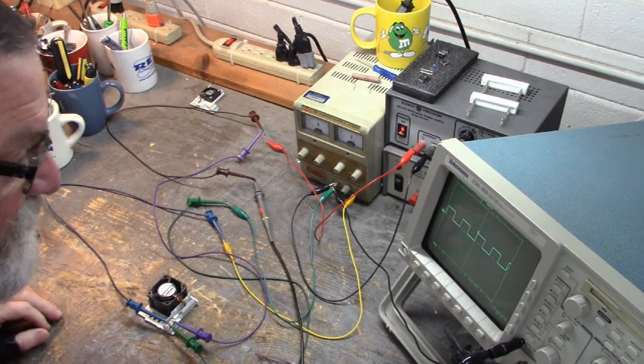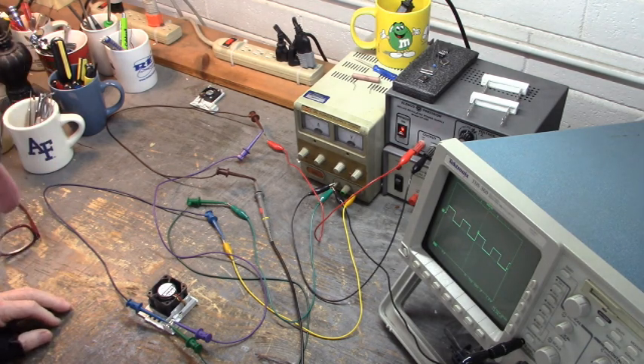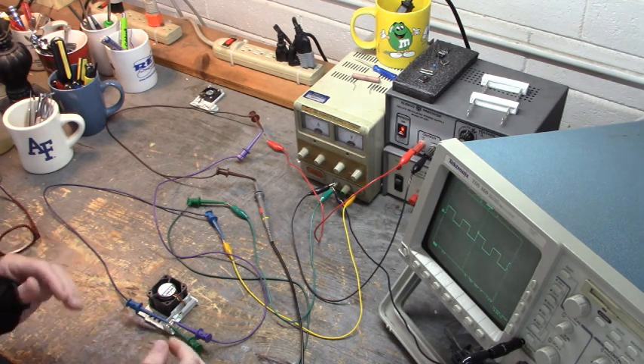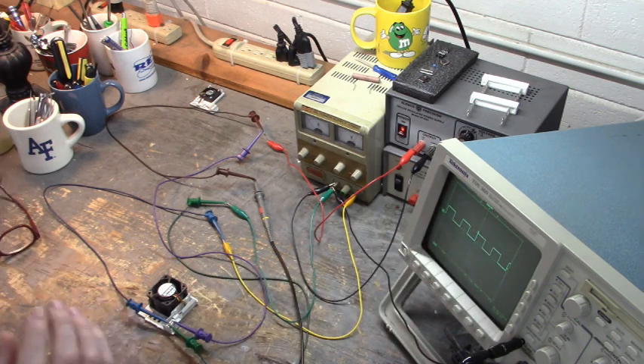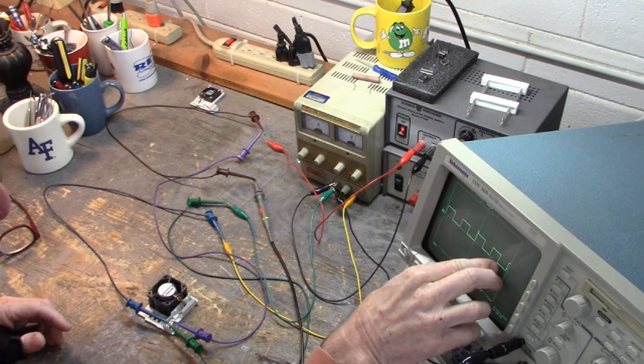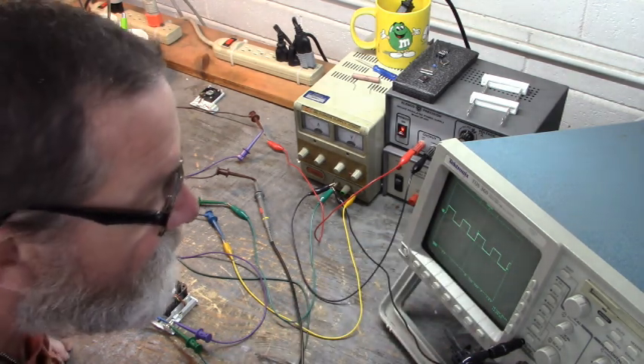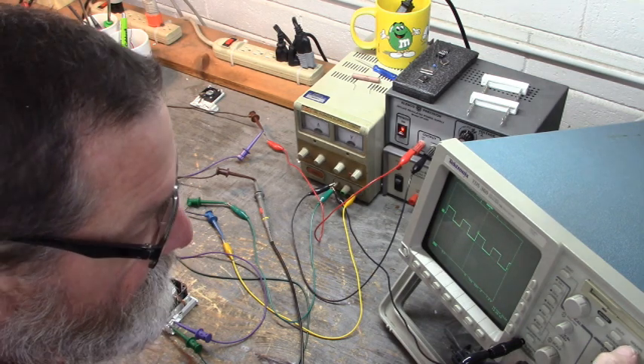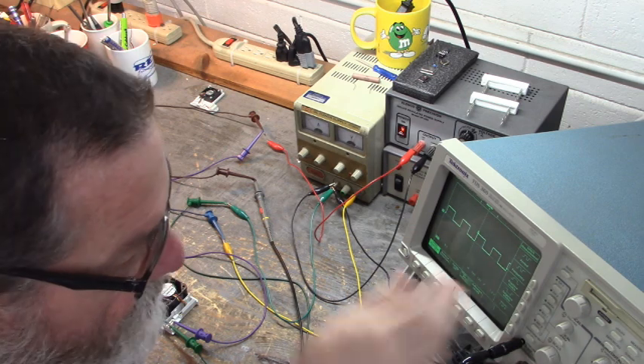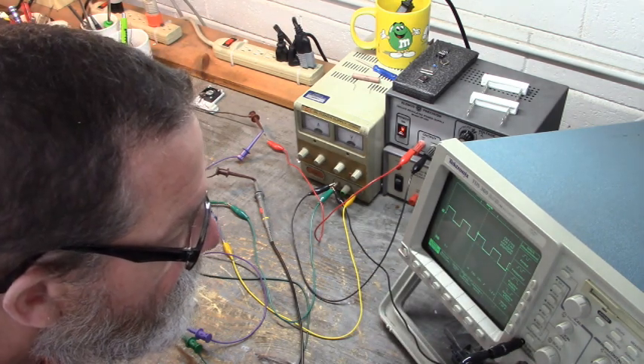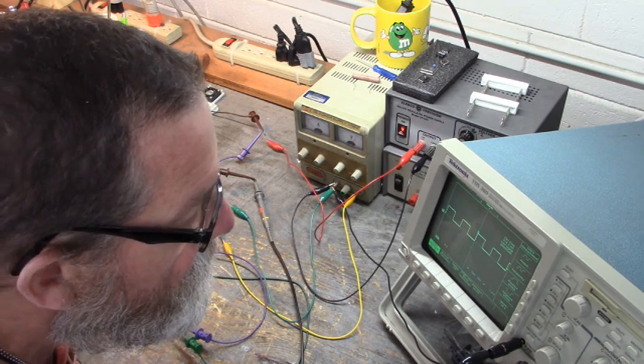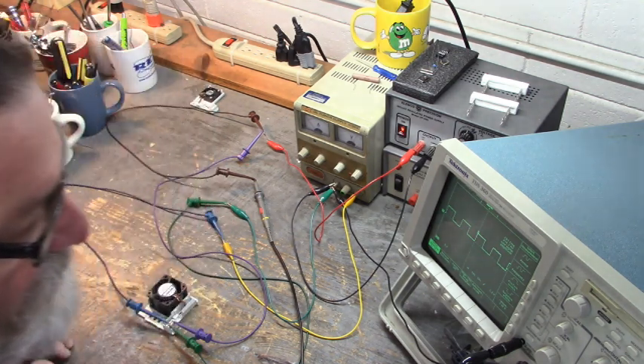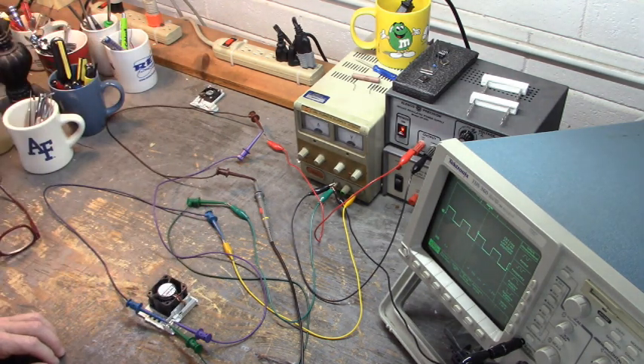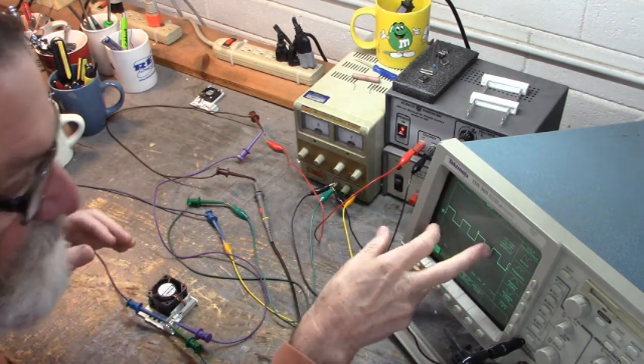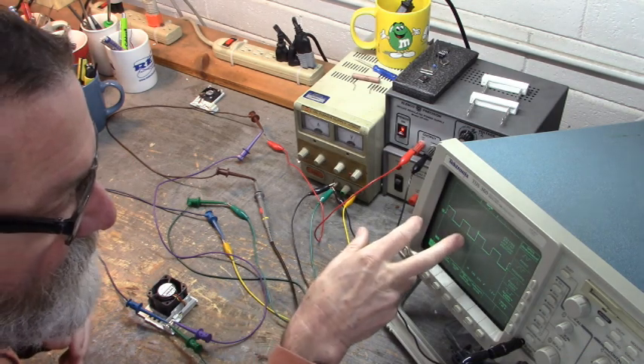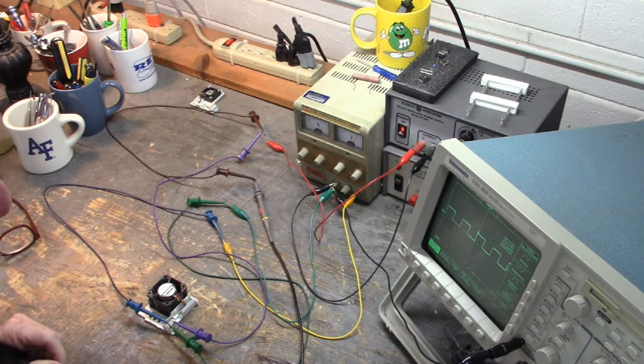So on some 3-wire cooling fans that have the fan running signal, when the fan is running, the output would be high, and others when the fan is running, the output would be low. But in our case, we have a square wave. Now I wonder what that frequency is. Set our scope to measure the frequency. That says about 416.7 hertz. So when that drive sees our square wave of 416 hertz thereabouts, that drive knows that cooling fan is running.